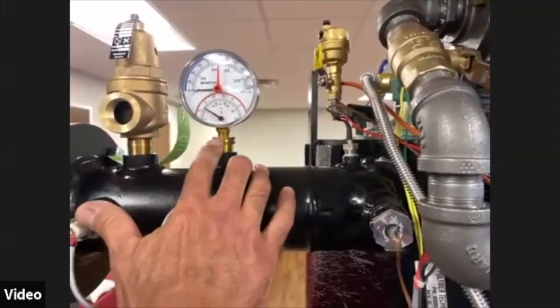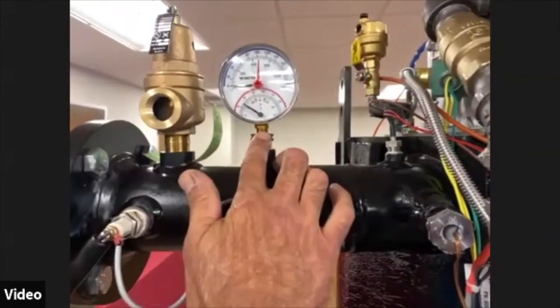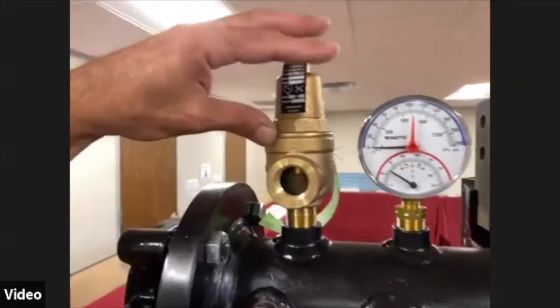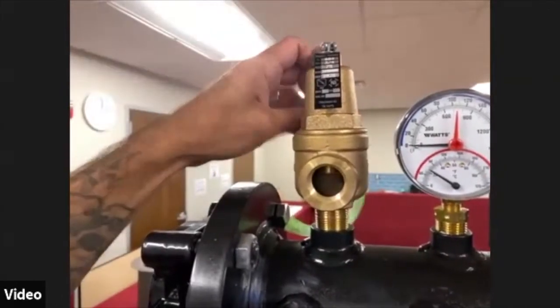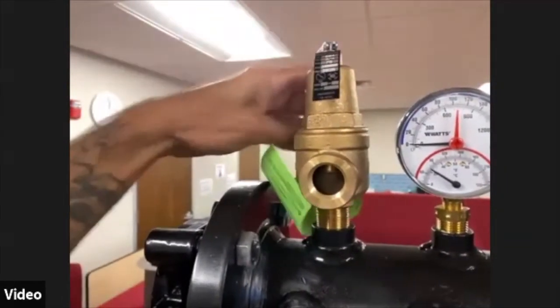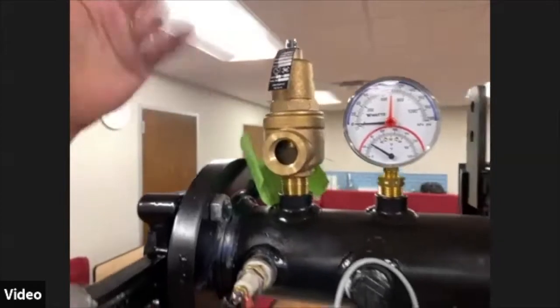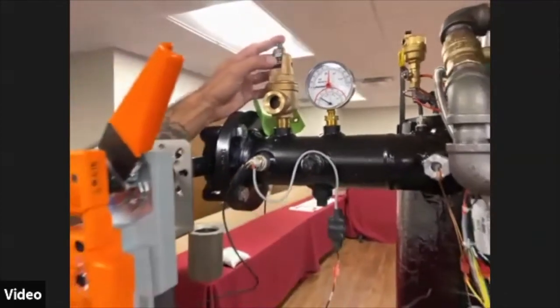Coming across the header, we have our tridicator or pressure temperature gauge, and we have our pressure relief valve. Pressure relief valve testing, basically it's just a trip lever. So trip the lever, make sure that the relief valve actually does relieve and that it reseals.